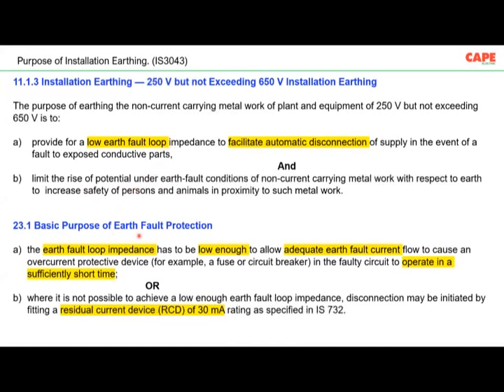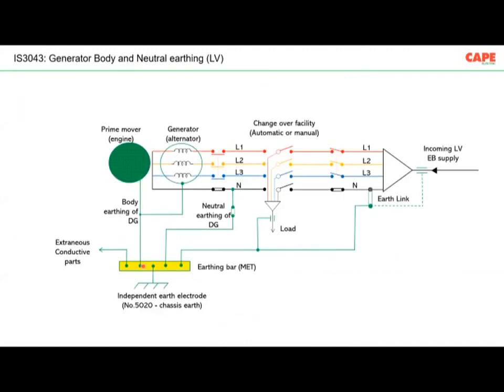Now, if you look at clause number 23.1, basic purpose of earth fault protection: the earth fault loop impedance has to be low enough to allow adequate earth fault current to flow to cause an overcurrent protective device to operate within a sufficiently short time. What this says is, in a normal installation, earth fault protection is achieved by disconnecting a protective device, which is nothing but a fuse or an MCB. Similarly, where it is not possible to achieve a low enough fault loop impedance, the disconnection is achieved by an RCD. So these conditions are very well explained in this standard.